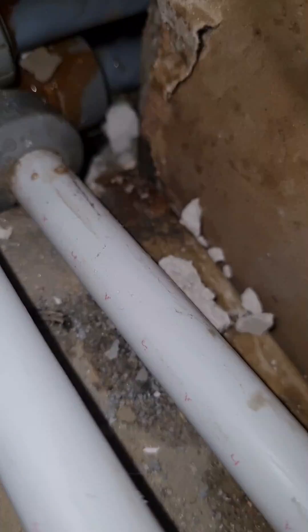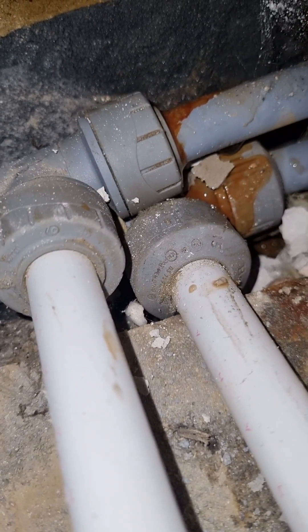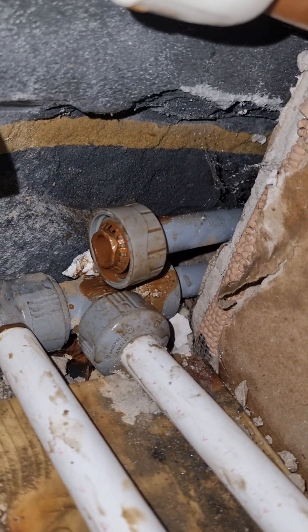And I found the culprit. Not liking the look of these fittings. You can see the top one is leaking, but I'm going to change them both just to be safe. When I disconnected the fitting, it doesn't look like the pipe was pushed in far enough.